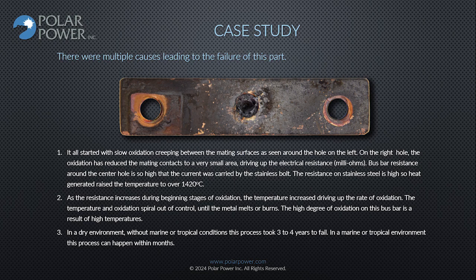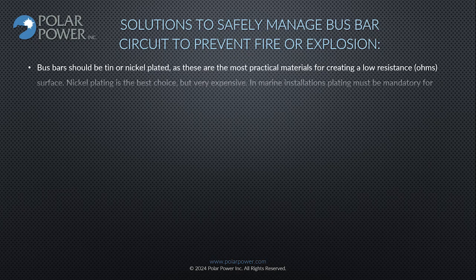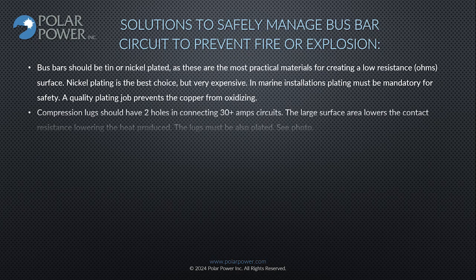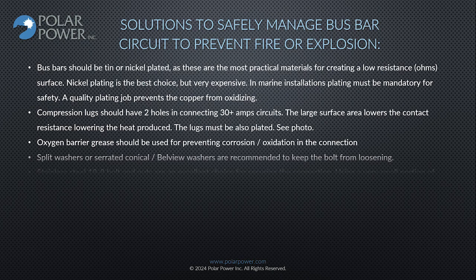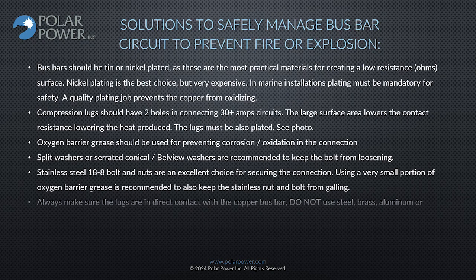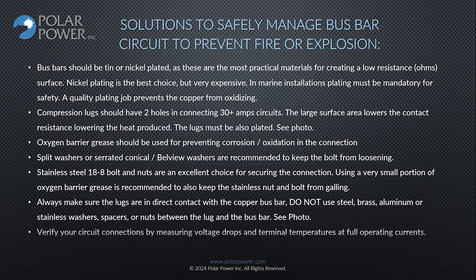The high degree of oxidation on this bus bar is a result of high temperatures. In a dry environment, without marine or tropical conditions, this process took 3 to 4 years to fail. In a marine or tropical environment, this process can happen within months. Solutions to safely manage bus bar circuit to prevent fire or explosion: Bus bars should be tin or nickel plated, as these are the most practical materials for creating a low resistance ohms surface. Nickel plating is the best choice, but very expensive. In marine installations, plating must be mandatory for safety. A quality plating job prevents the copper from oxidizing.